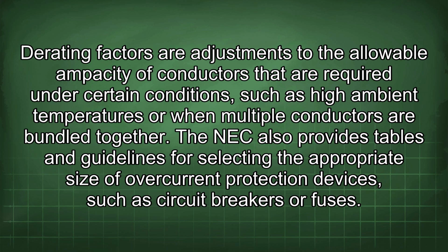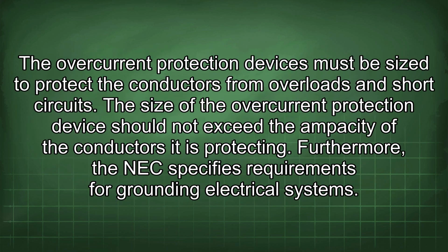The NEC also provides tables and guidelines for selecting the appropriate size of overcurrent protection devices, such as circuit breakers or fuses. The overcurrent protection devices must be sized to protect the conductors from overloads and short circuits. The size of the overcurrent protection device should not exceed the ampacity of the conductors it is protecting.